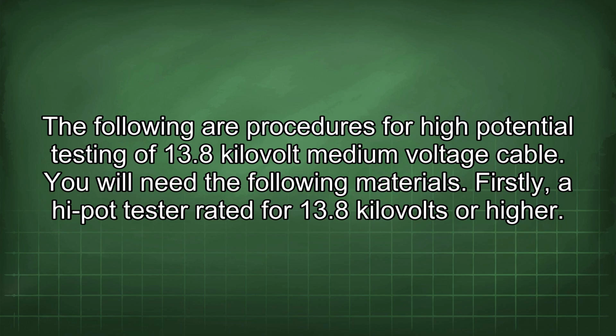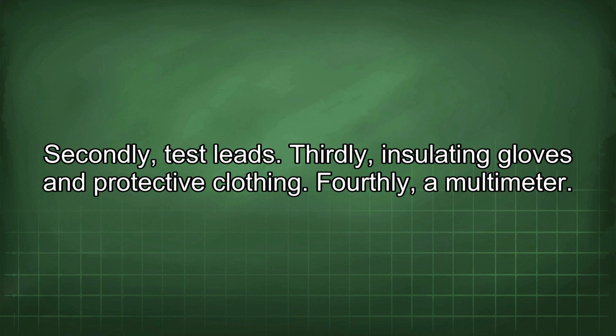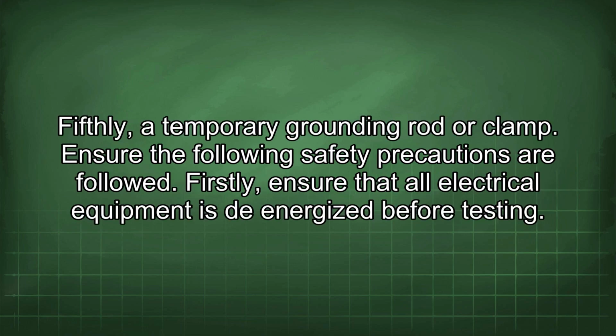You will need the following materials. Firstly, a hi-pot tester rated for 13.8 kV or higher. Secondly, test leads. Thirdly, insulating gloves and protective clothing. Fourthly, a multimeter. Fifthly, a temporary grounding rod or clamp.